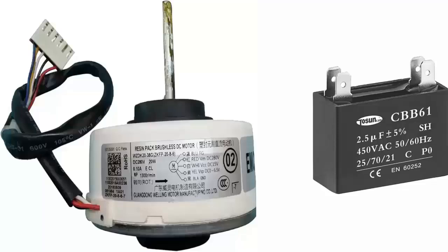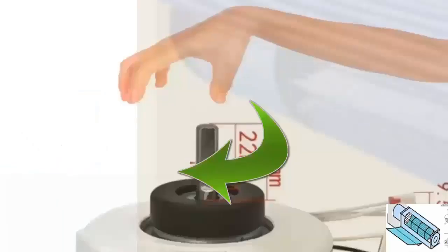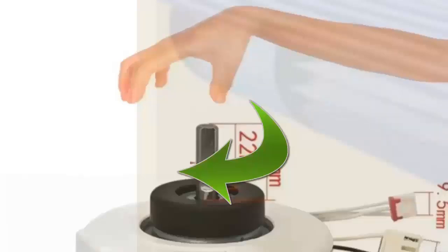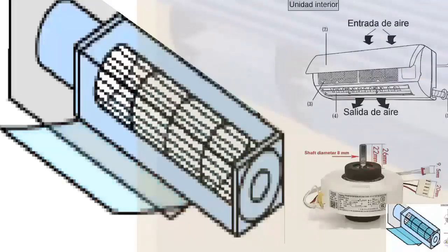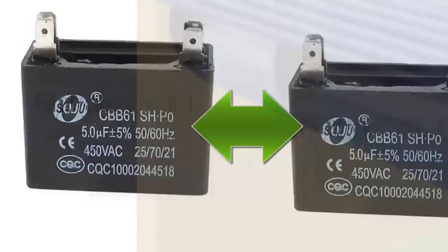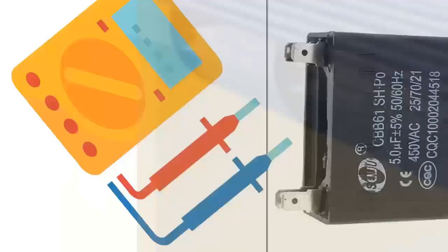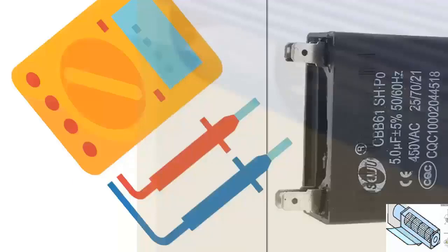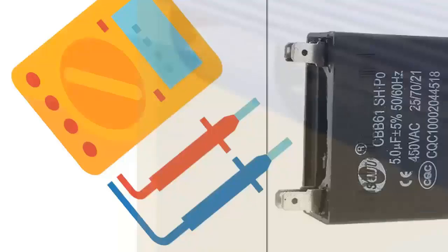1. Capacitor Failure: If the fan emits a humming noise but does not move, try to start it manually. If it starts, the problem is likely the capacitor. Check the capacitance value of the capacitor and test with another capacitor of similar value if available. If there is no replacement capacitor, discharge it electrically and measure its capacitance with a multimeter to verify if it is within normal parameters.